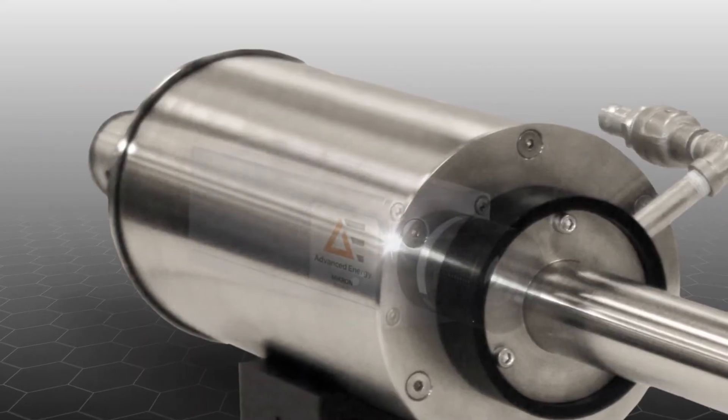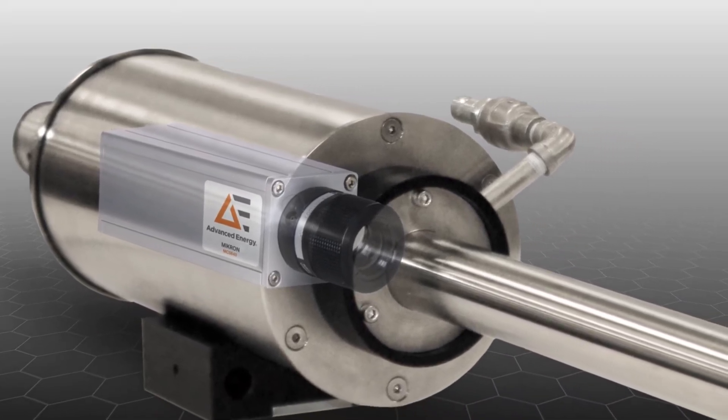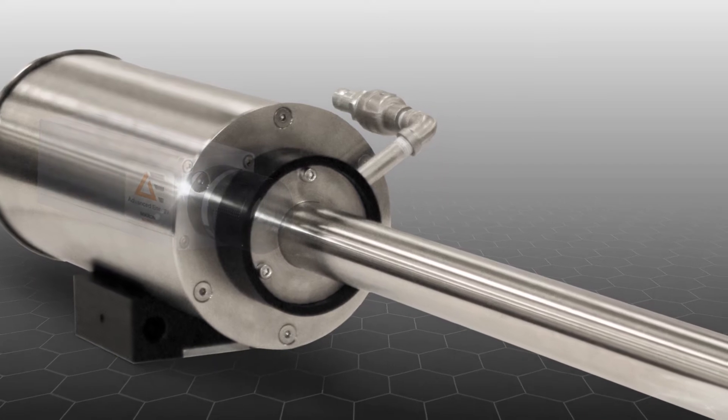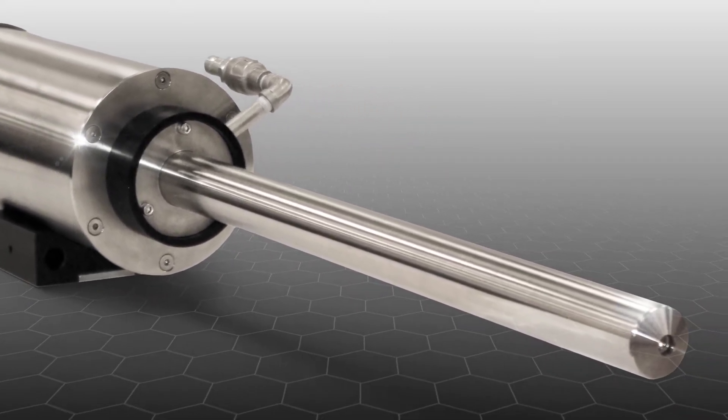It features a 640 x 480 pixel thermal imaging camera with heavy duty bore scope optics, achieving a clear resolution with a wide field of view that captures about 72% of the inside furnace area.